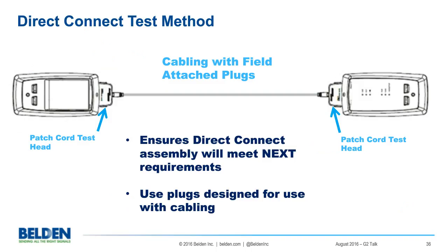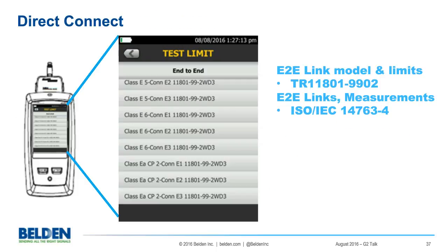So I make a direct connect assembly, I put my plugs on, and I test it. What does that test look like? Well, the test limit is called out. It's also called end-to-end. Right now, it's a link model and limit. It's a TR technical report 11801-9902 that's being developed in the ISO IEC community that is going to become a spec under ISO IEC 14763-4. That's coming up. It's going to be sometime next year. But for now, these test limits are available for use, and if you use these, they will ensure that the field attached plug will achieve the performance that you expect.